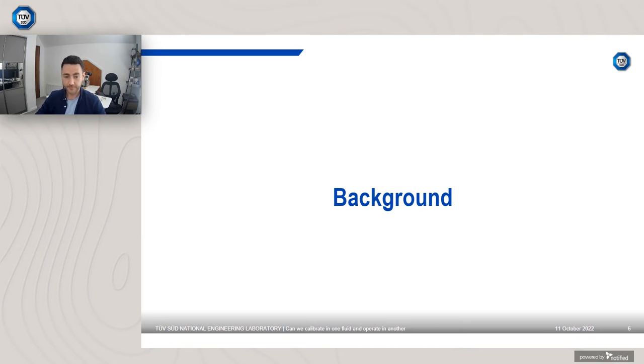So in terms of background, as I said, the title of this webinar is "Can we calibrate in one fluid and operate in another?" Now, there are a few parts to that question, depending on how you focus on it or interpret it. If you send your flow meter to a calibration laboratory anywhere, it doesn't need to just be NEL. We are, of course, the designated institute for flow in the United Kingdom. If you send your meter to a calibration laboratory, you're already going to be calibrating in a different fluid to the one that you operate in. It's highly unlikely that it's going to be a perfect match.